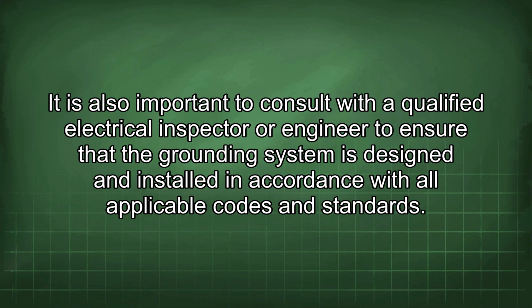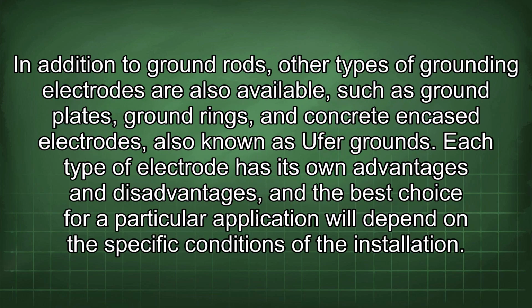It is also important to consult with a qualified electrical inspector or engineer to ensure that the grounding system is designed and installed in accordance with all applicable codes and standards. In addition to ground rods, other types of grounding electrodes are also available, such as ground plates, ground rings, and concrete encased electrodes, also known as Ufer grounds.